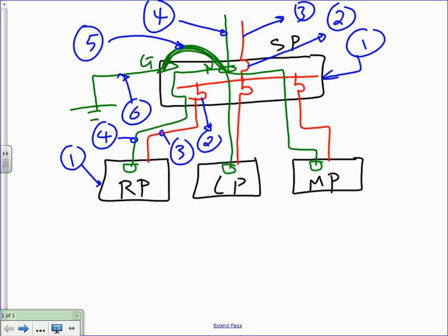Okay, so does that make sense? We have a service panel, and from this service panel we're feeding, typically, guys, a receptacle panel, a lighting panel, and a mechanical panel. Most commercial buildings almost always take this format, and we're supposed to size all this system. Any comments, guys, before we move on? This is going to be similar to the project that we do, and we're going to be testing you guys on it.